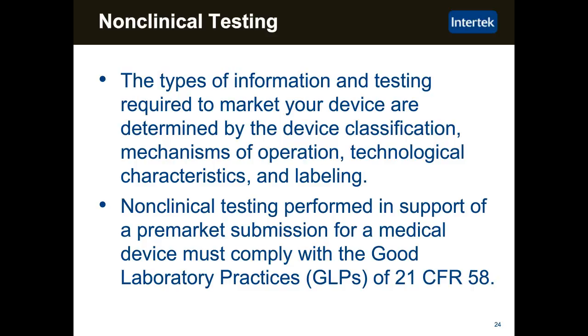So another factor to consider is that non-clinical testing performed in support of a pre-market submission for a medical device is supposed to comply with good laboratory practices, which are also government regulations, Part 58, Title 21 of the Code of Federal Regulations. And it's very good for people to review these requirements because, as a company that helps people put their 510Ks in, we see a lot of pushback from the FDA when the data and the reports that are supplied don't comply with GLPs, don't have good traceability on the materials, and that becomes a problem for the processing of the 510K and causes delays in getting the product to market.